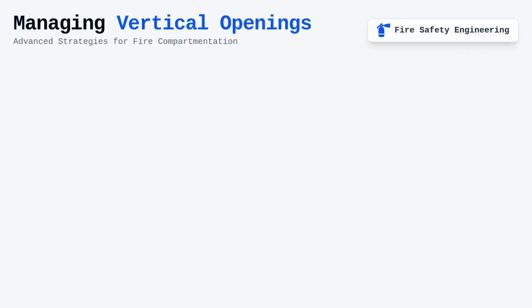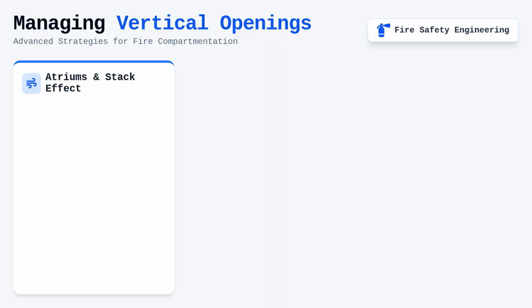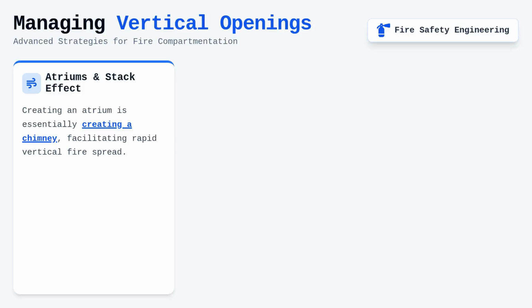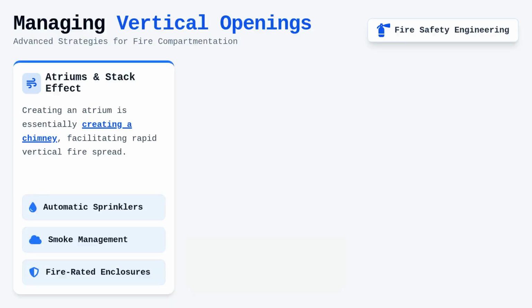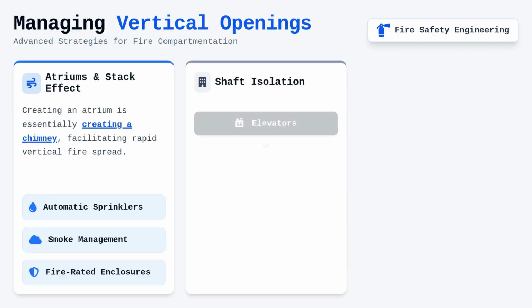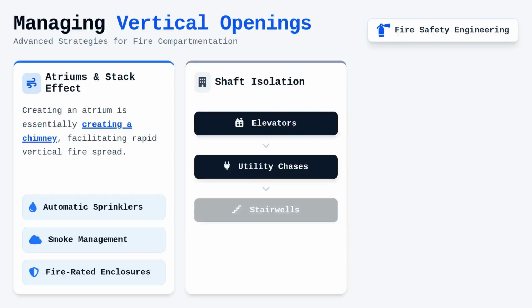Managing vertical openings like atriums and shafts is perhaps the most challenging aspect of compartmentation, as these features naturally facilitate the stack effect and the rapid vertical spread of fire. When we design an atrium, we are essentially creating a chimney, which is why the code demands specific combinations of automatic sprinkler protection, smoke management systems, and fire-rated enclosures. Shaft protection is equally critical.